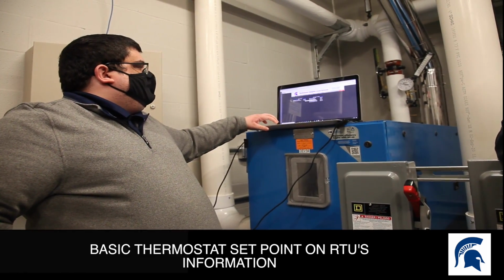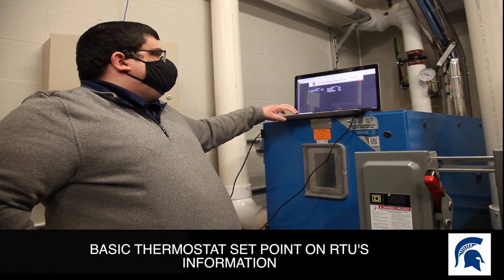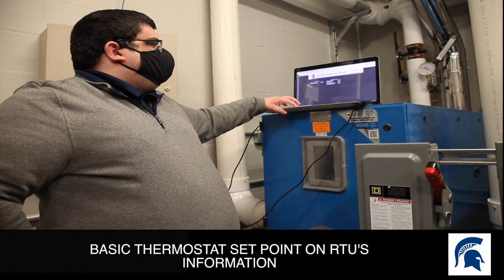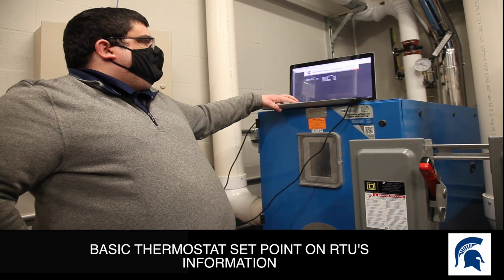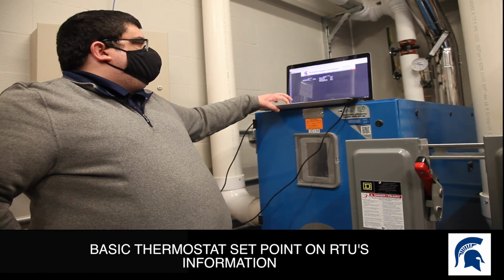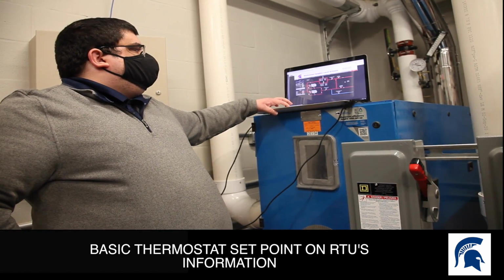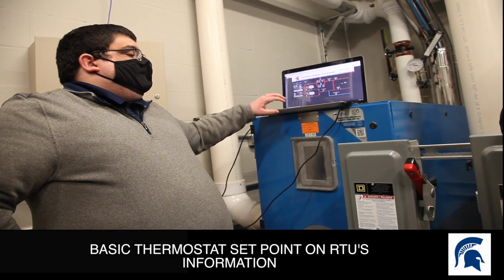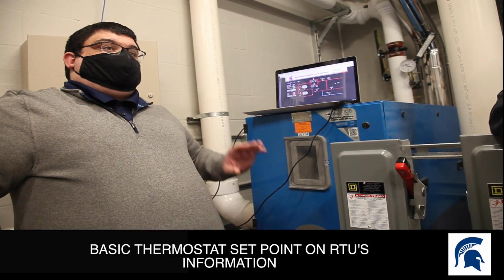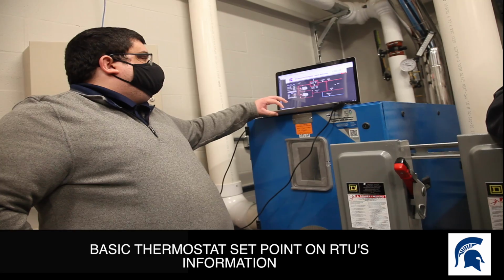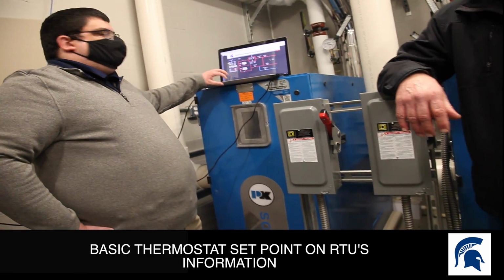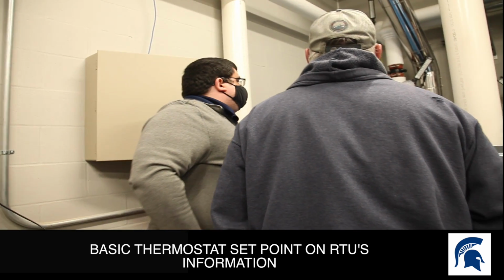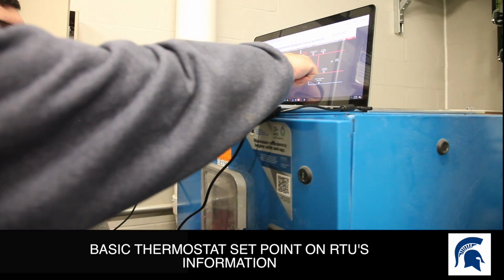You have your set point there, which was at 22, and then here's your hot water reset to let you know you should have 151 degree water. That's what the system wants, the set point that it wants to have. If you come back onto the main page, your actual supply temp right now is only 131. Here's your return. Arrows going out, arrows coming in.